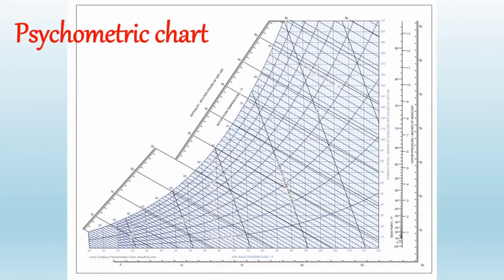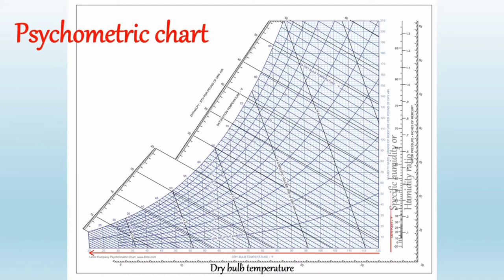So this is a psychrometric chart. In a psychrometric chart, dry bulb temperature is taken as the abscissa — that means on the x-axis — and specific humidity or humidity ratio, that is moisture content, is on the y-axis. The saturation curve is drawn by plotting the various saturation points at corresponding dry bulb temperatures. The saturation curve represents 100% relative humidity at various dry bulb temperatures, and it also represents the wet bulb and dew point temperatures.